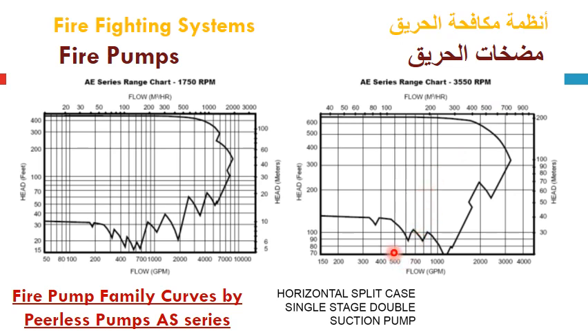So for example, if we have the pump discharge 500 GPM with 300 feet, our operating point will be located here as shown with this marking point, which is included on an HQ curve located somewhere here. But this curve just gives us the family name and the construction and the model type of this pump, and we can study the HQ curve of this pump carefully in each separate and specific HQ curve in the catalog later on.